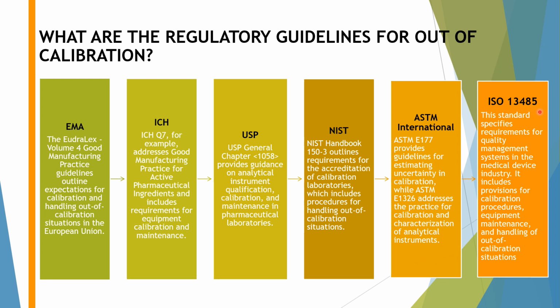Next is ISO 13485, International Organization for Standardization 13485. This standard specifies requirements for the quality management system in the medical device industry, right? It includes provisions for calibration procedures, equipment maintenance and handling of out of calibration situations, right? So these are the guidelines which talk about the handling of out of calibration results, right?